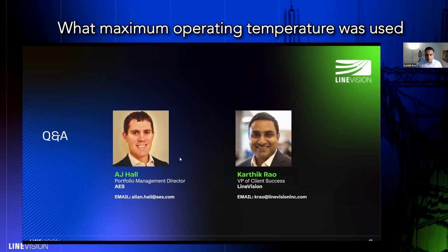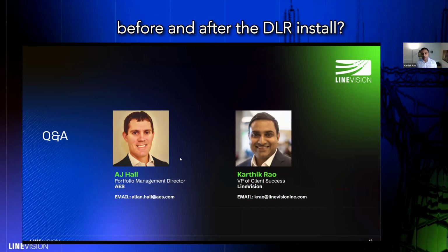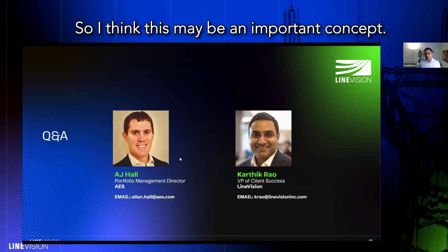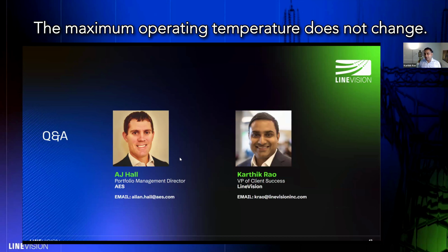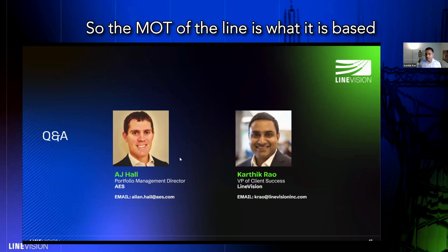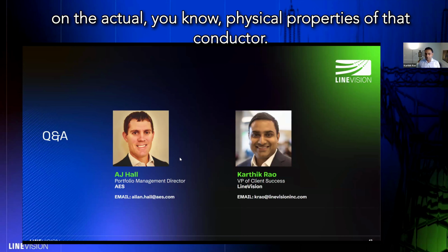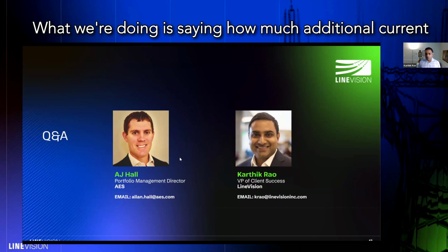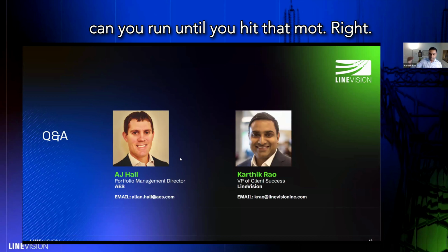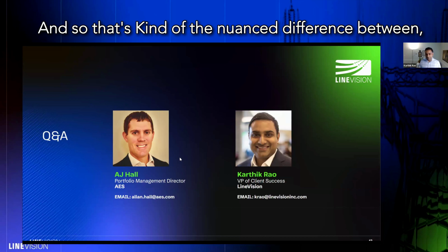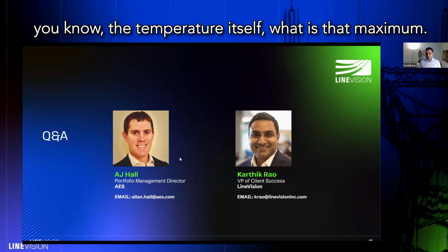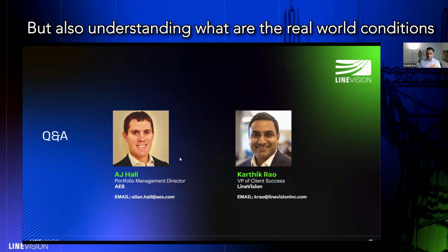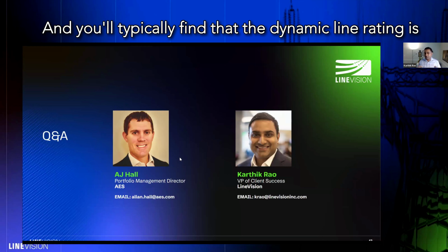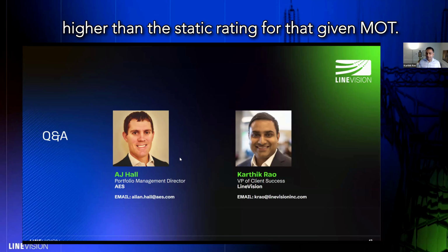What maximum operating temperature, or MOT, was used before and after the DLR install? That's an interesting question. The MOT of the line doesn't change, it's based on the actual physical properties of that conductor. What we're doing is asking how much additional current can you run until you hit that MOT. That's the nuanced difference between the temperature itself and understanding the real world conditions that allow you to run up to that MOT. You'll typically find the dynamic line rating is higher than the static rating for that given MOT.